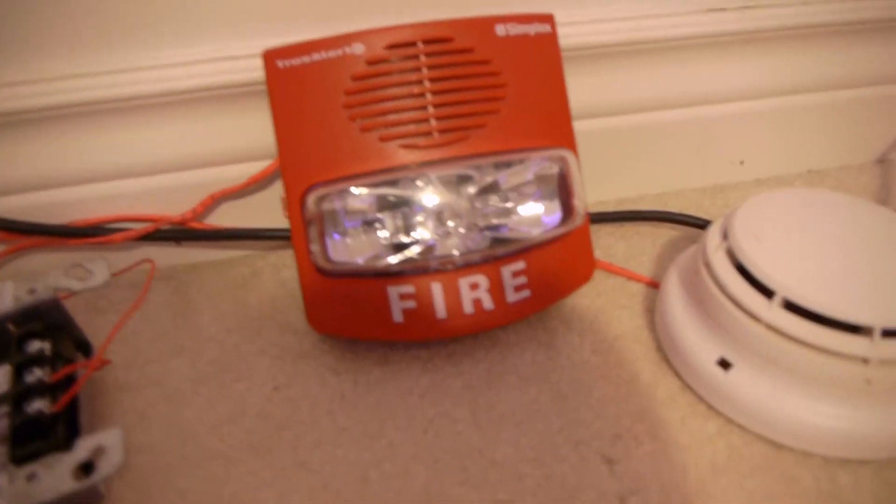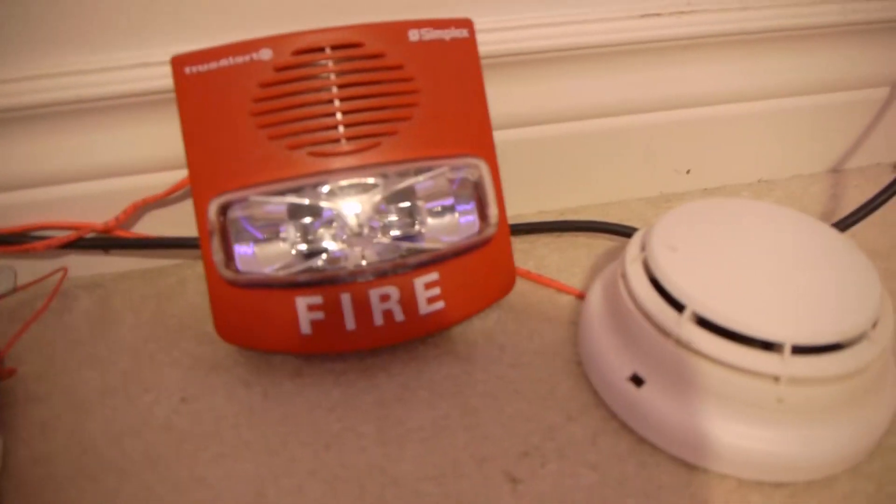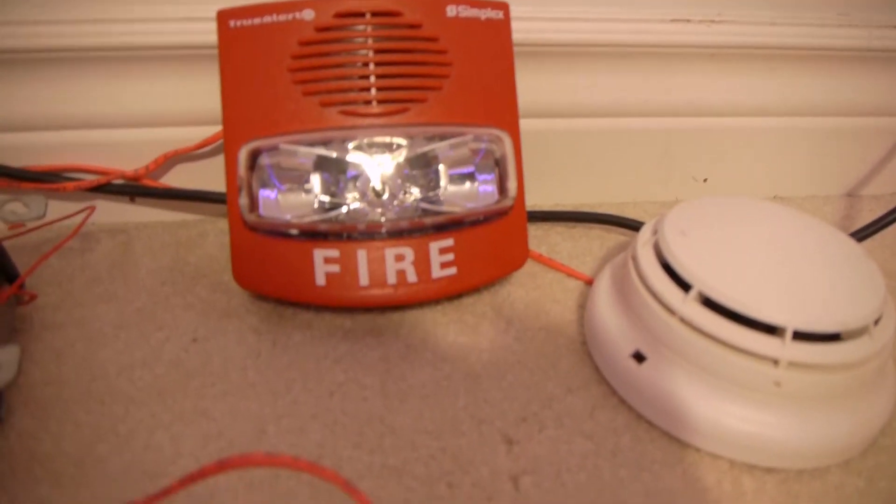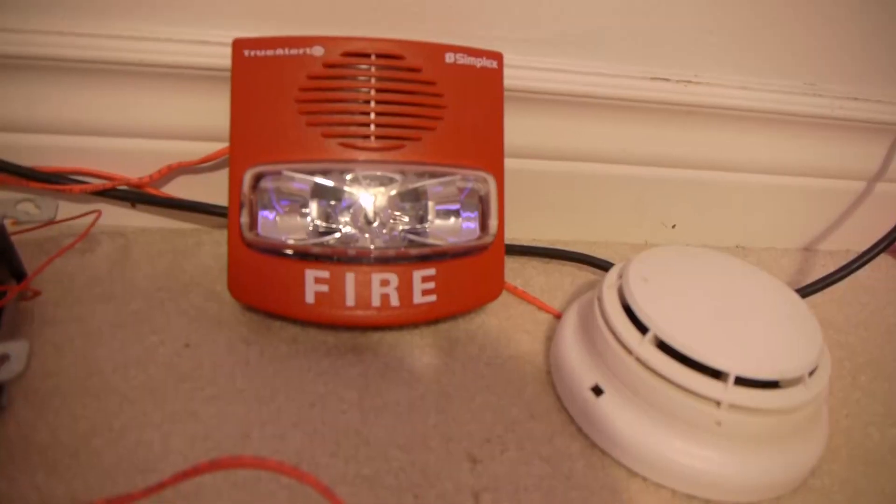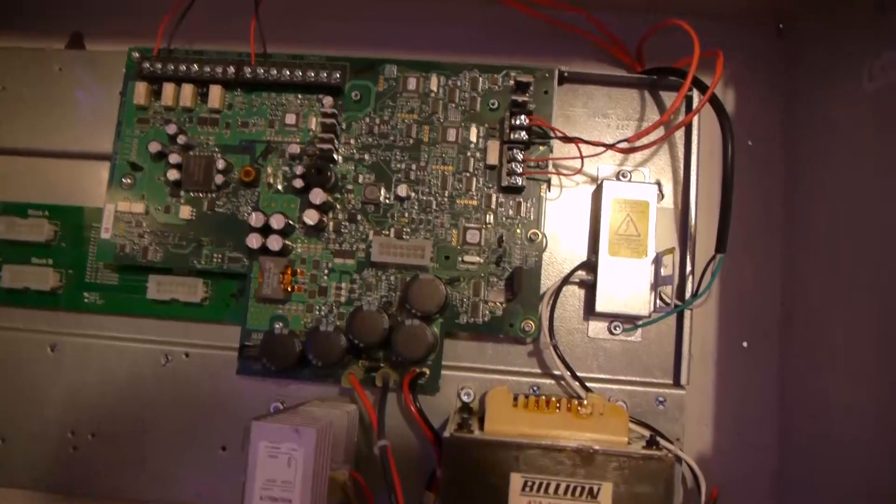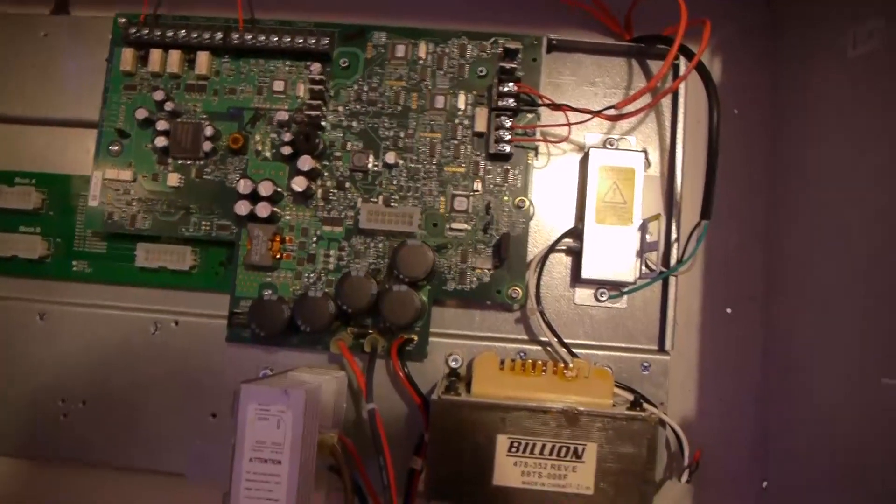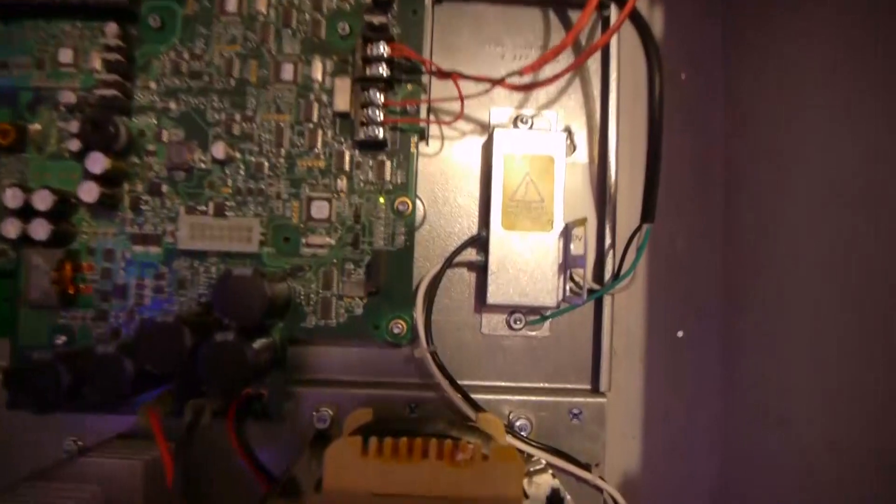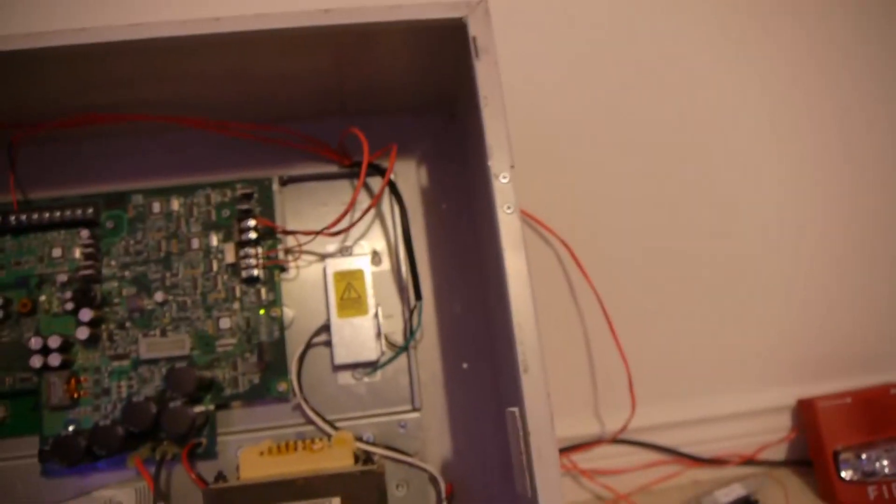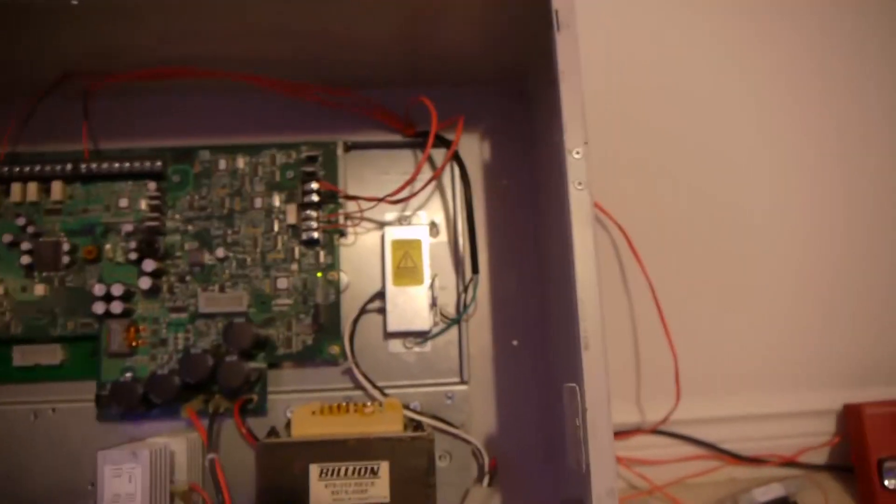Now on this panel it uses TrueAlert ES addressable devices, and you should see that blink. So all the AVs for this are addressable normally, this does not have any normal NAC circuits, except for technically the relay can be programmed as a NAC circuit if you wanted to. So yeah, that's the basic setup here.